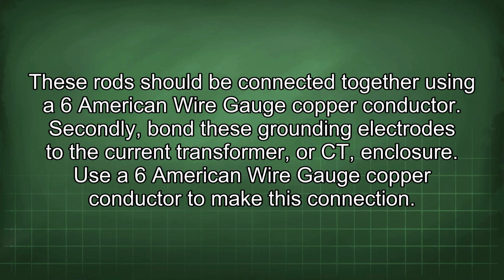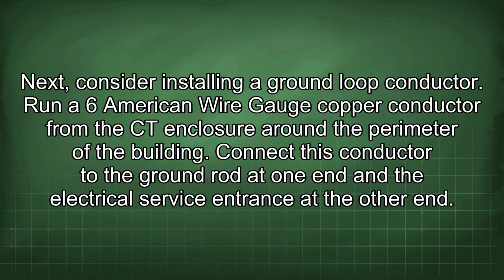Secondly, bond these grounding electrodes to the current transformer, or CT, enclosure. Use a 6 American wire gauge copper conductor to make this connection. Next, consider installing a ground loop conductor. Run a 6 American wire gauge copper conductor from the CT enclosure around the perimeter of the building. Connect this conductor to the ground rod at one end and the electrical service entrance at the other end.